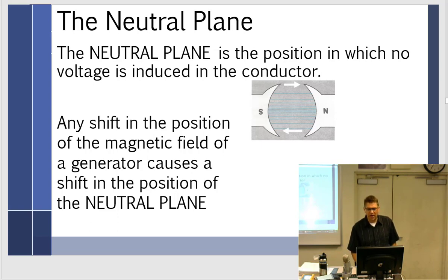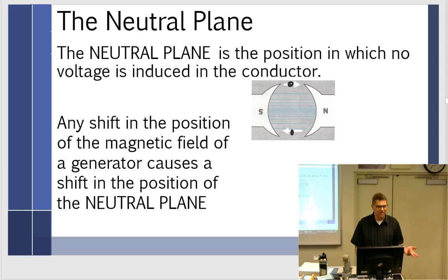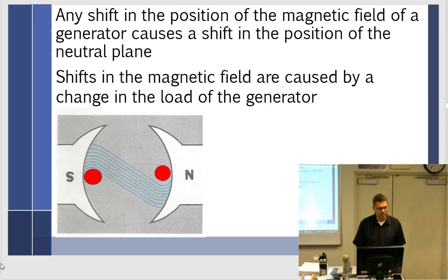Having an armature here and another loop and saying 'there's the neutral plane' assumes you have no shift in the lines of flux — that they go nice and neat from north to south. But we're going to shove in not one loop of wire but an armature containing all kinds of loops of wire. What's going to run through it? Current. Current running through a loop of wire is going to create a magnetic field, which will interact with the main field and cause distortion.